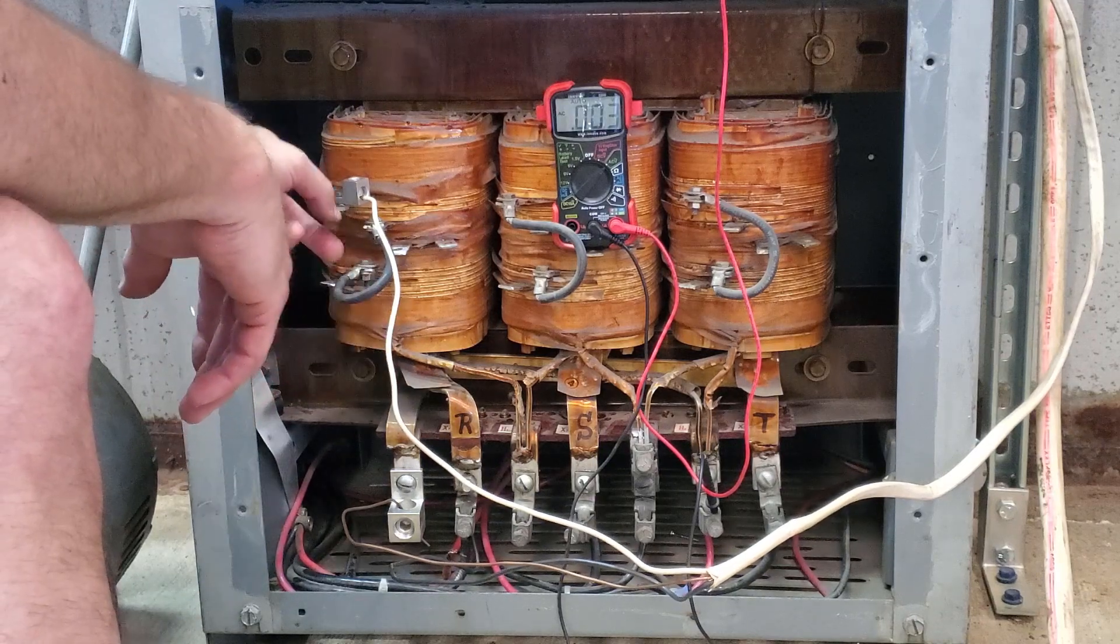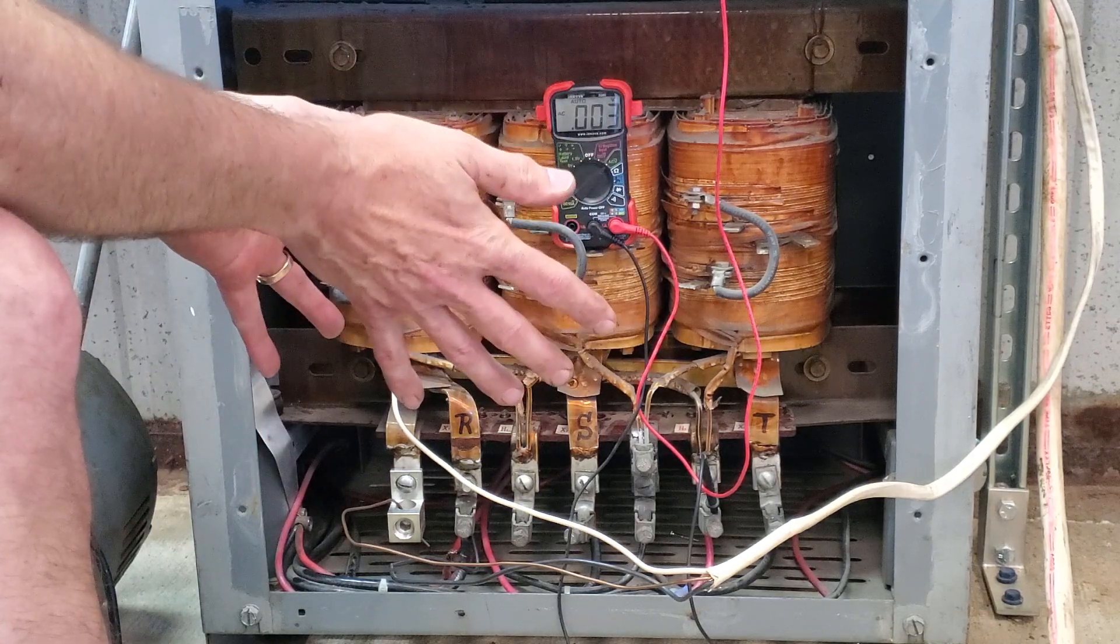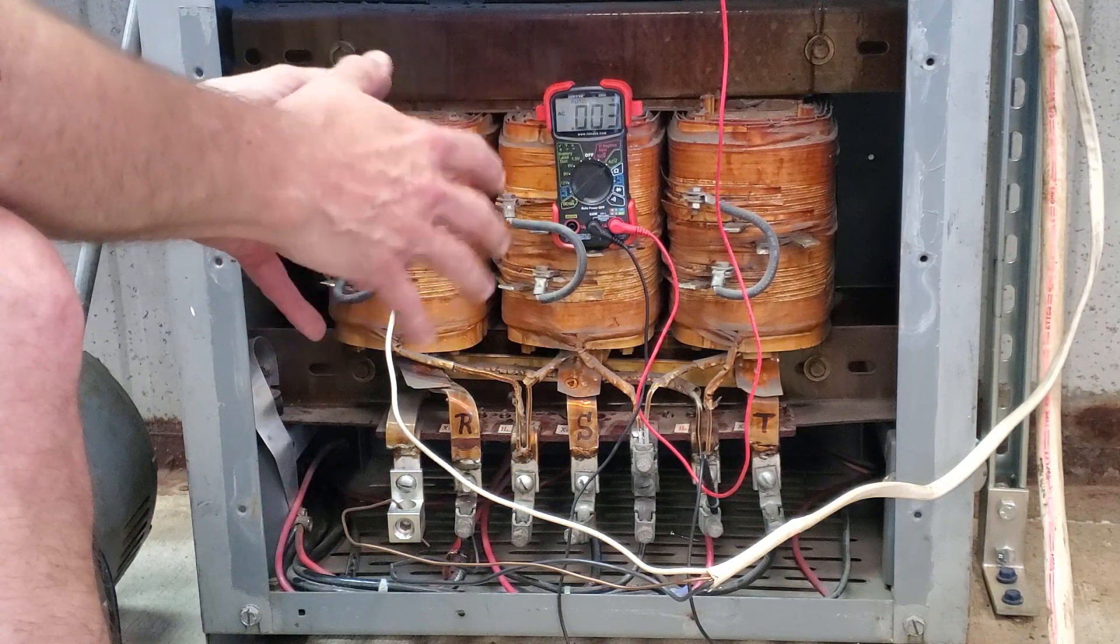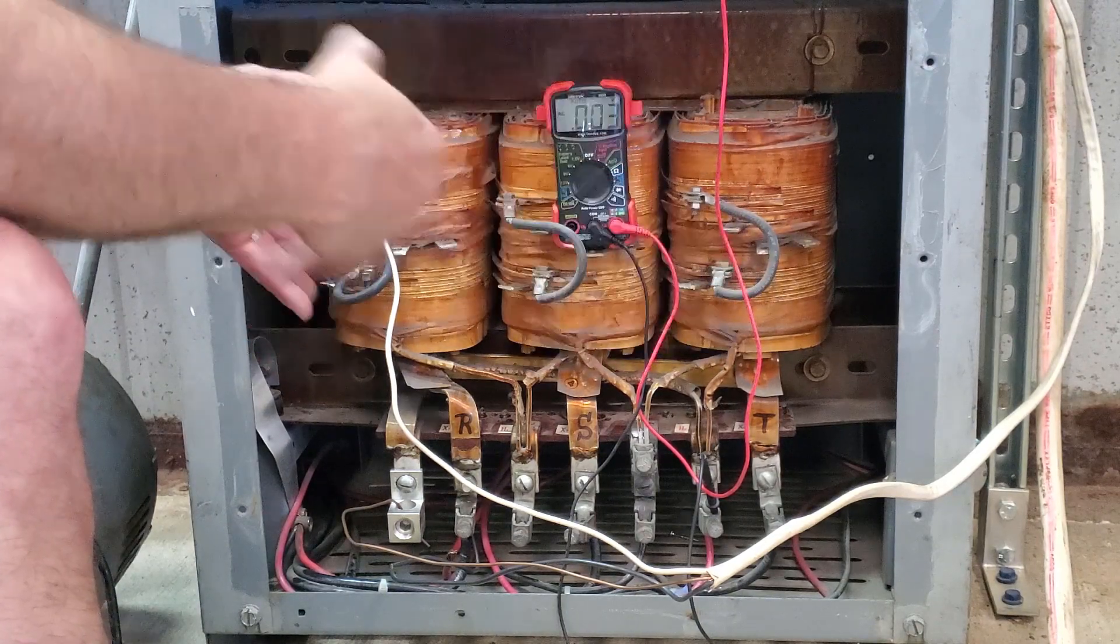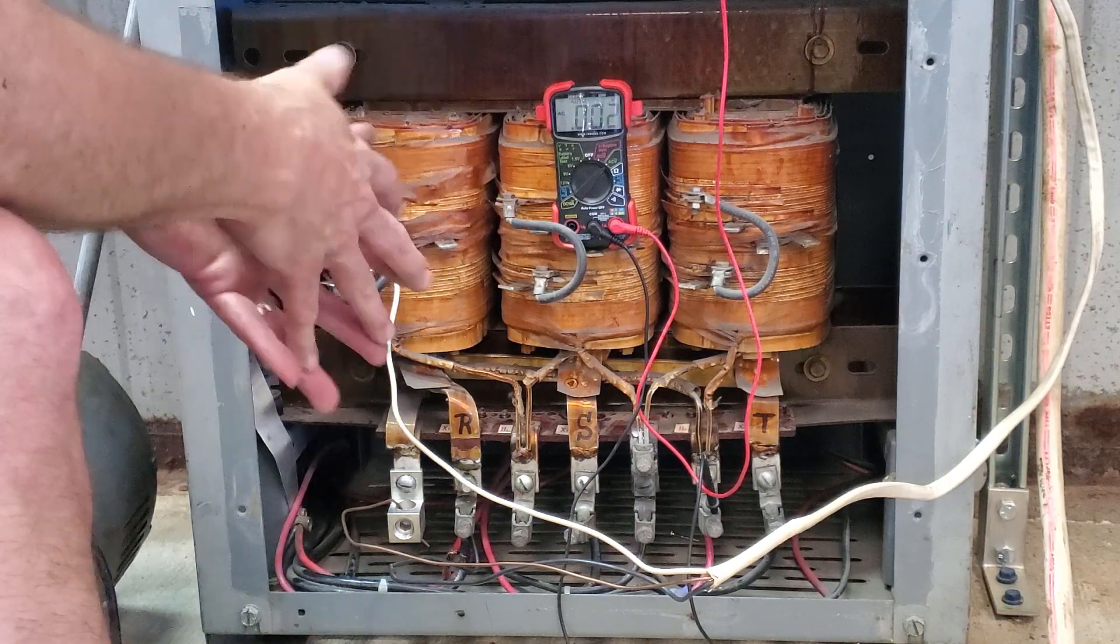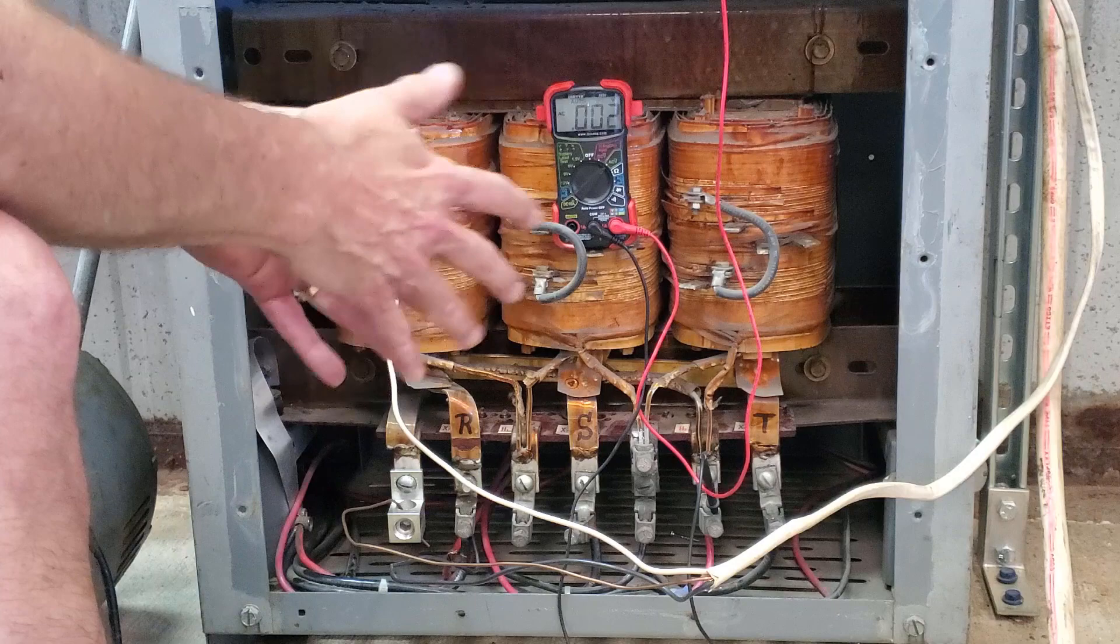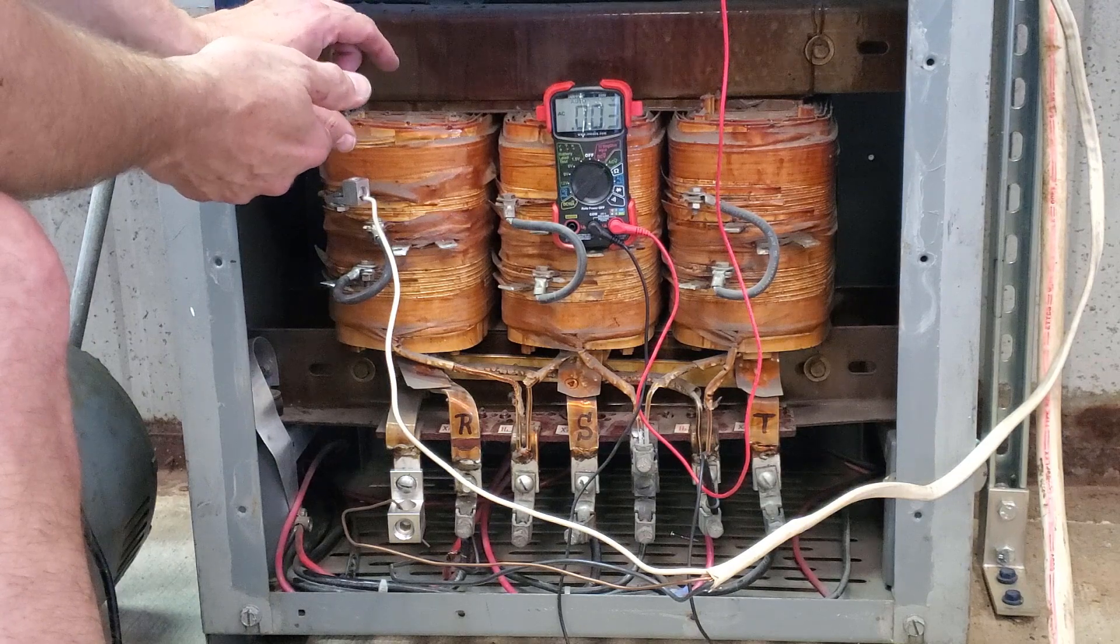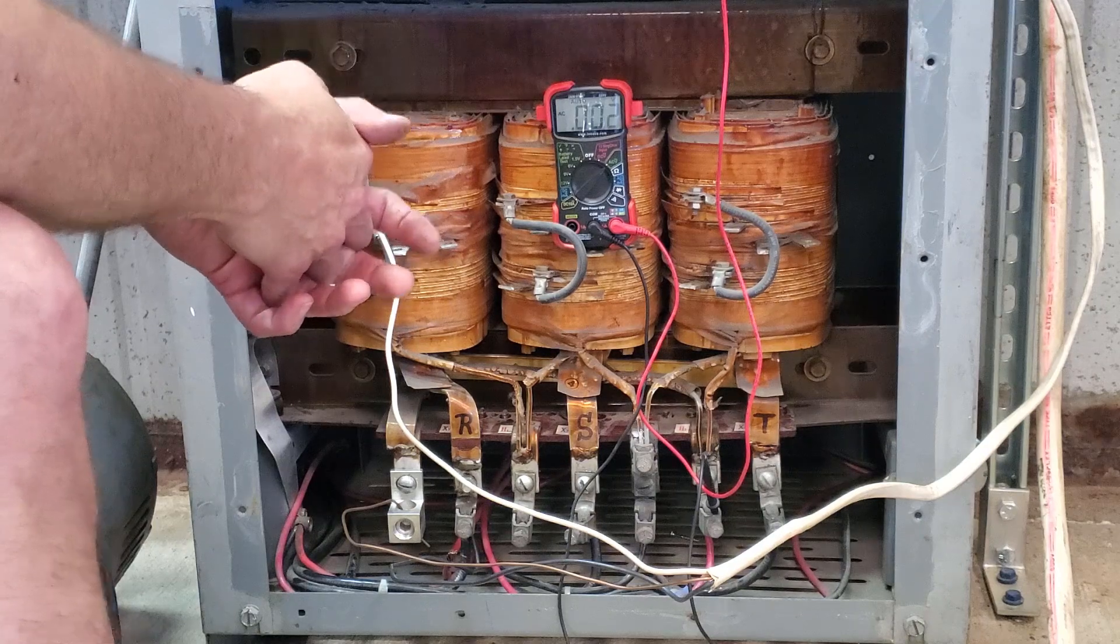So I've got the probe on the H3, I'm going to measure the voltage at H1 once I power up. But the other thing that you'll notice is there's a ground on this upper tap here. Grumpy Old Man said because a delta transformer setup has no ground, you can tie one of the points to ground to limit how far any of these voltage points get from ground. Otherwise it can kind of float and be anywhere. So the point that I'm tying is the topmost tap. That's going to give me about 400 volts on one side and like 77 volts on the other side. That's the closest point to center that I could get.